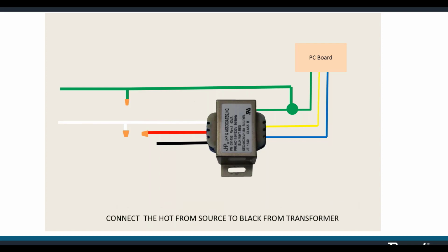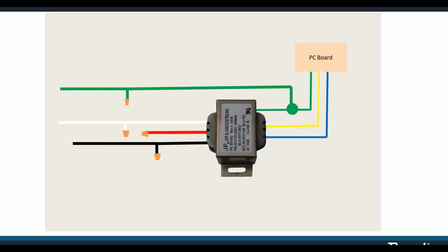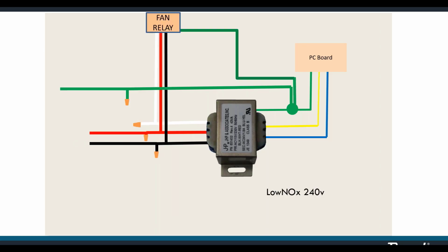And the remaining wire is our hot, and we will connect that to our black coming from the transformer. Wired properly, you'll have 24 to 29 volts coming out the other side and plugged into the board. Now, since we're talking about the Low NOx model today, I would point out that the fan runs full power. So that has to be connected to the power source before the transformer.